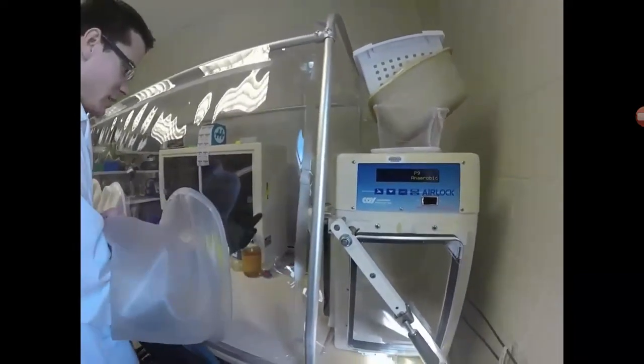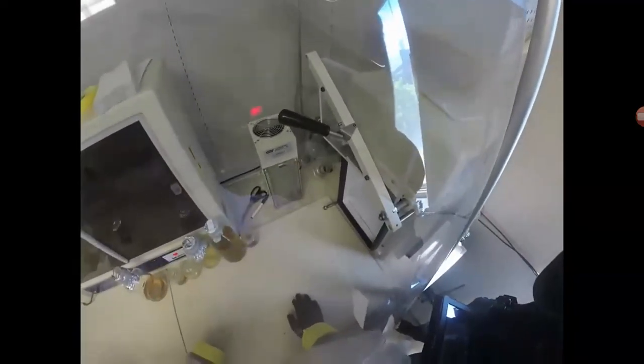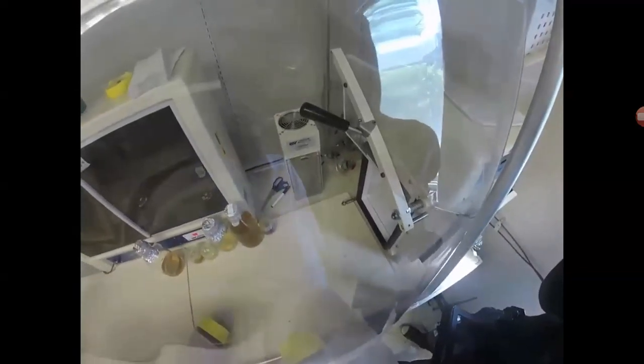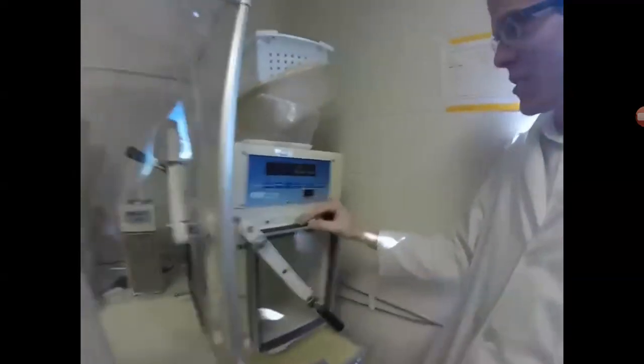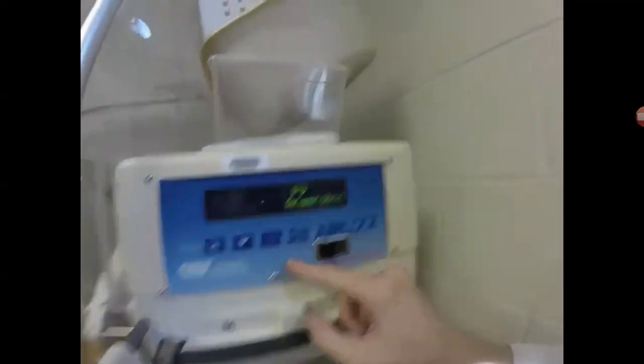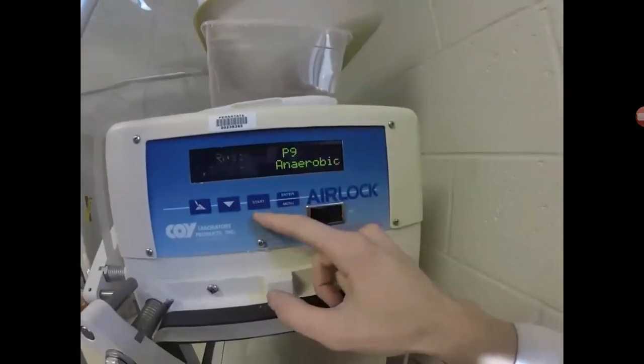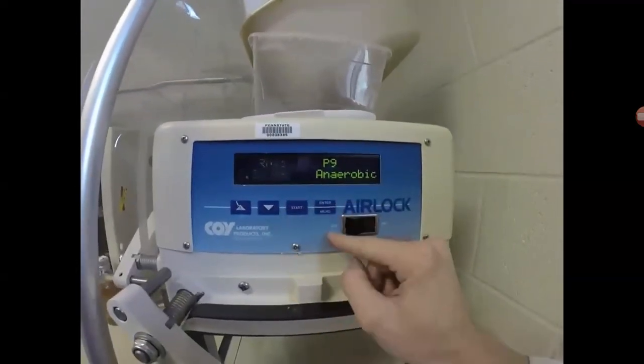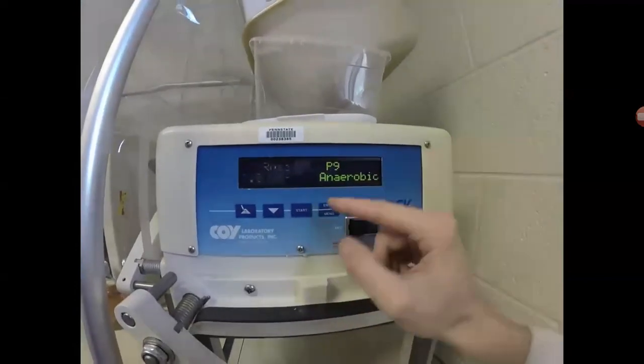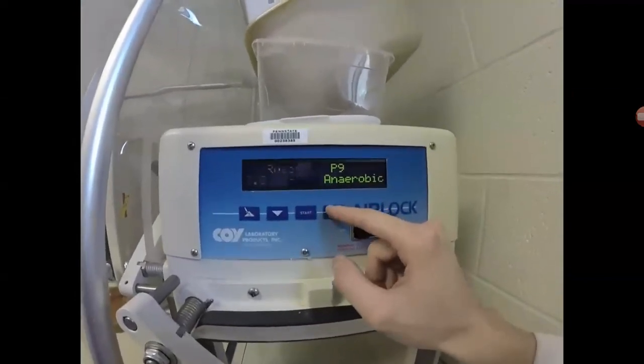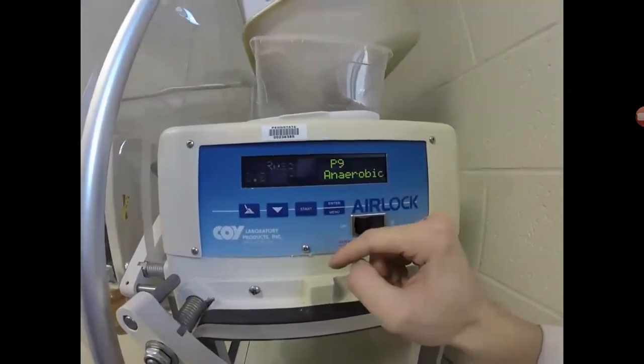So carefully, let's put our hand in here. Open the door just like that. We're going to leave that door open because we're actually going to refill the chamber to get the hydrogen concentration back. I'm going to teach you how to use manual mode now, which is actually fairly easy. So you can come back over to this screen. Previously we just used the start button to start the process to make the chamber airlock anaerobic. Now we're going to manually adjust, pull vacuum and insert gas.